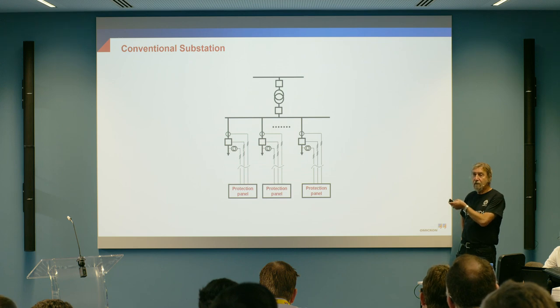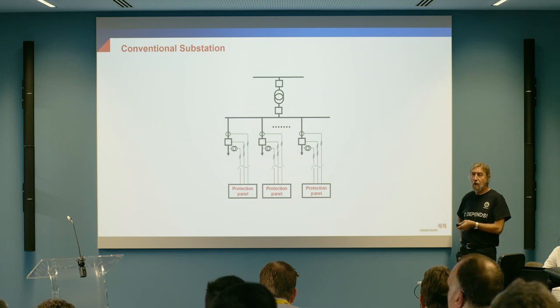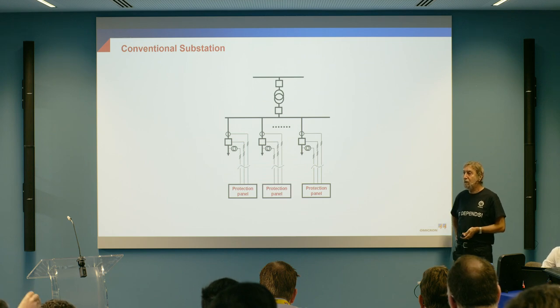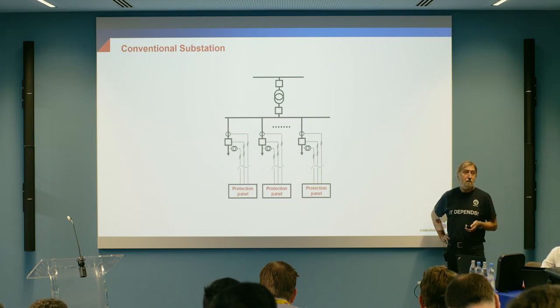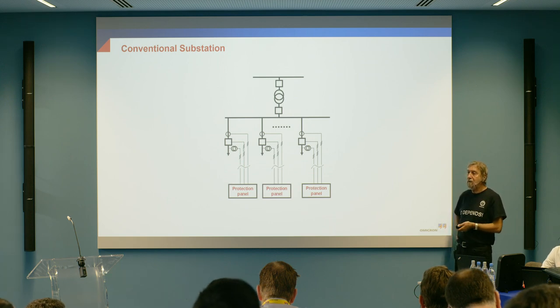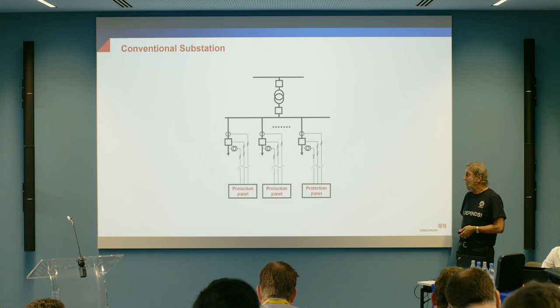Because when you have these long wires bringing the currents from the substation yard to the control house to the relays — the electromechanical relays with high burden — one of the big issues we were facing was CT saturation. So we had to design our systems in such a way to try to minimize the effect of the CT saturation, or to use protection technology that can handle this kind of issue.